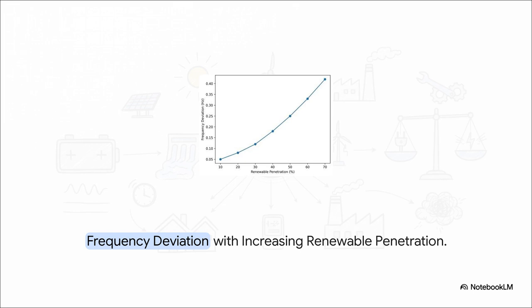Down at 10 or 20% renewable energy, the deviation is minimal because those old heavy spinning machines are still carrying the load. But when renewable penetration hits 70%, the frequency deviation spikes dangerously high. Without that physical flywheel effect, the rate of change of frequency, engineers call this RoCoF, happens so insanely fast that it can actually trigger under-frequency load shedding, which, by the way, is just technical jargon for rolling blackouts.